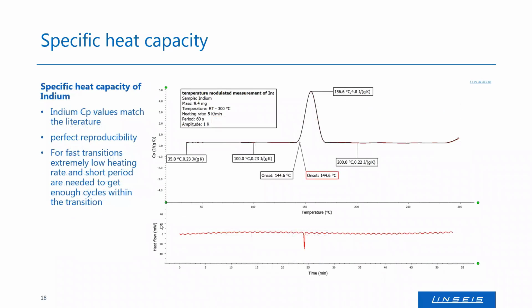Okay, normally we should choose a calibration material that's almost similar to our sample. So if you measure, for example, a metal, you should calibrate with a metal and not with a polymer, because the heat capacity and mostly also the weight are really different here. But I want to check if it's still possible with the chip DSC and temperature modulation to get valuable CP values if I measure some metals. So I've tested this with indium. I've measured the indium 3 times, and what you can see here are 2 measurements of this indium. And the reproducibility is quite good.